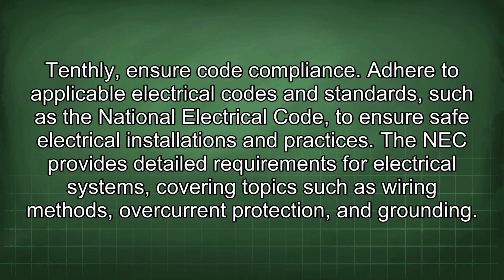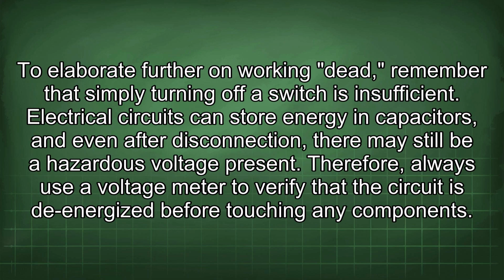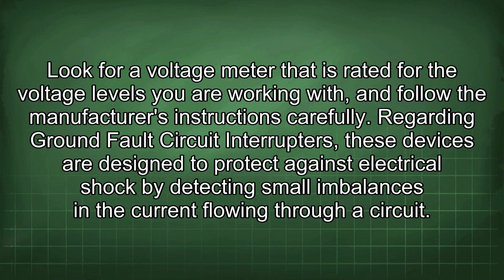To elaborate further on working dead, remember that simply turning off a switch is insufficient. Electrical circuits can store energy in capacitors, and even after disconnection there may still be a hazardous voltage present. Therefore, always use a voltage meter to verify that the circuit is de-energized before touching any components. Look for a voltage meter that is rated for the voltage levels you are working with, and follow the manufacturer's instructions carefully.